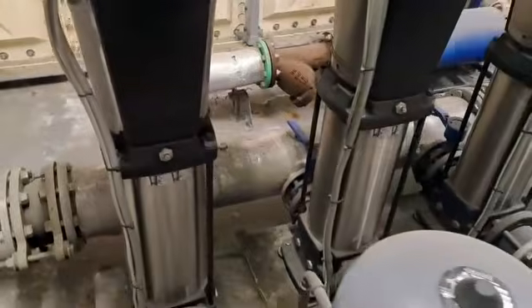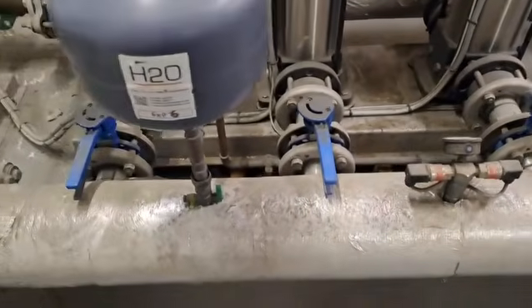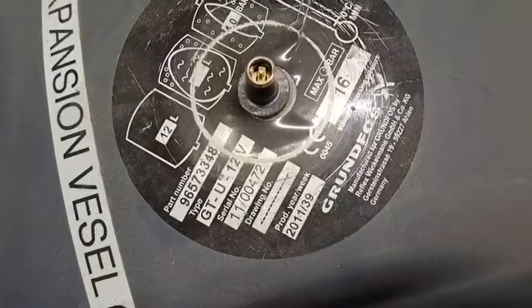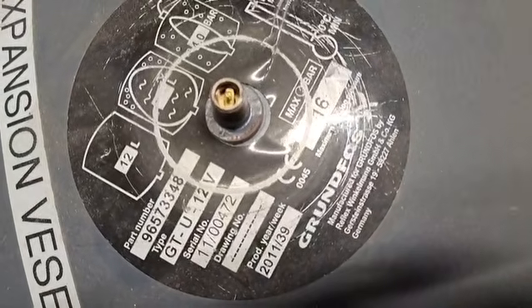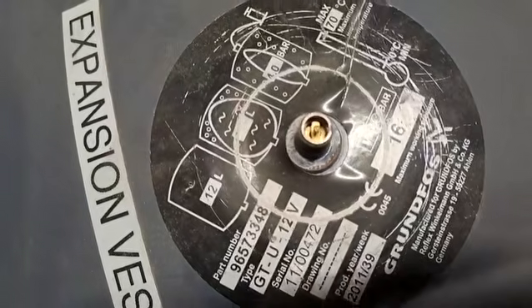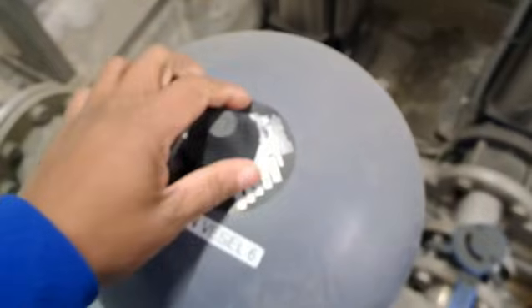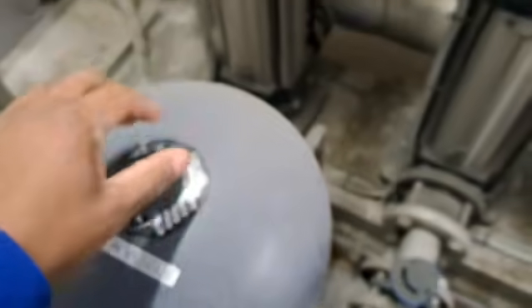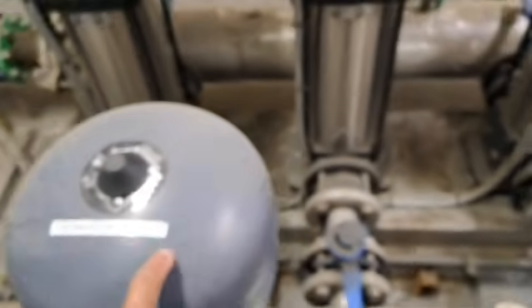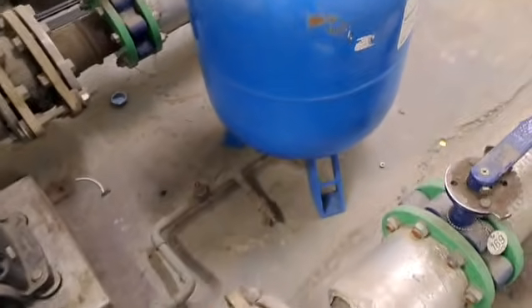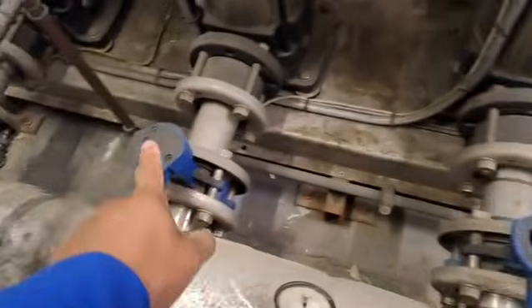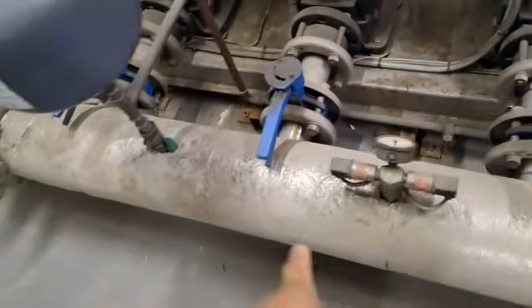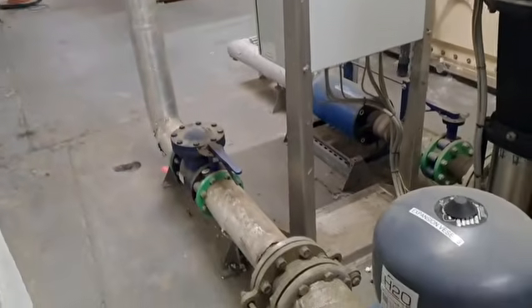So we obviously had it coming in from over there, and then it comes through and then gets boosted, and then we've got two expansion vessels. It's the year 2011, the 39th week since it's been in here. It's a 12 litre, pre-charged to 4 bar, but normally these would be charged to 0.5 less than what the system pressure is set to. So this has been set to 6 bar, so I'm assuming this is 5.5 bar. And then over here we have another expansion vessel, and you can see the pipework there comes up, and they're both connected to the outlet of the system.